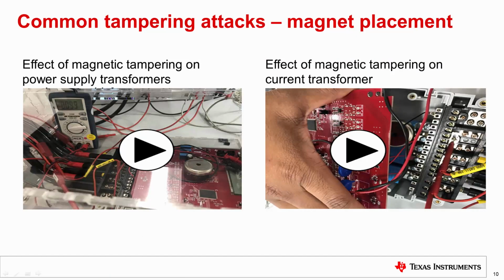To deal with magnetic tamper attacks, power supply transformers that are either magnetically immune or sufficiently magnetically resistant are used so that they could withstand these attacks. In systems that do not require a power supply transformer with a large drive, it is common to also see a cap drop transformerless supply used instead, since they are magnetically immune. Strong magnets can also affect current transformer current sensors. This video shows the effect of magnets on current transformers.